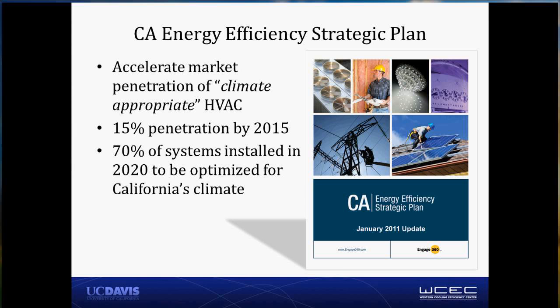Those give opportunity especially for using evaporation to improve the efficiency of HVAC operation. That can be done in a variety of ways. There's also other things we think of as climate appropriate, including operating or designing a conventional vapor compression system to have much higher effective sensible heat ratio, because as we see it, most commercial buildings in California don't need active dehumidification. They're very, very rarely controlled for active dehumidification, and frankly, much of the dehumidification that's done by conventional equipment amounts to an unneeded consumption of electricity. There's also opportunities for capturing efficiency by leveraging diurnal temperature swings in California, which are very large compared to the rest of the United States.